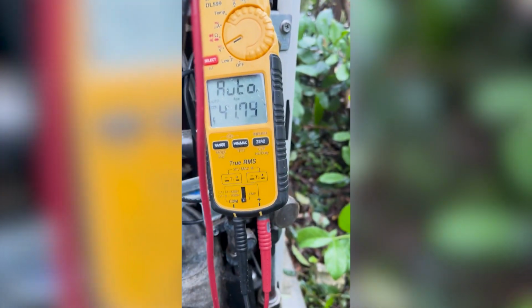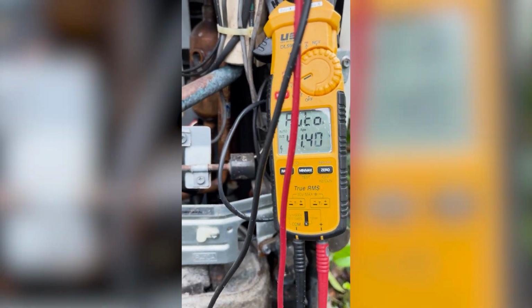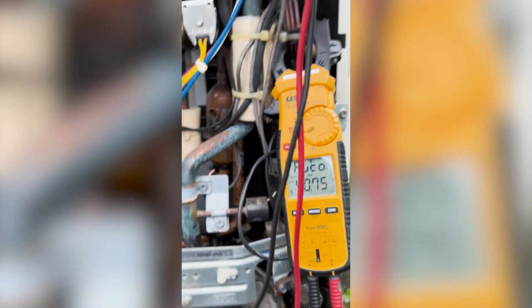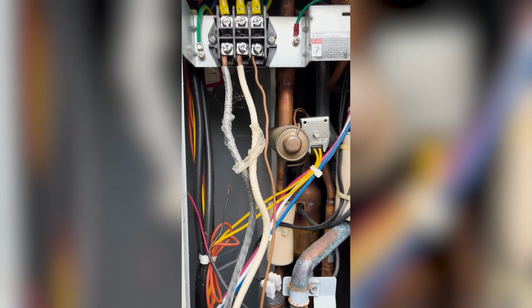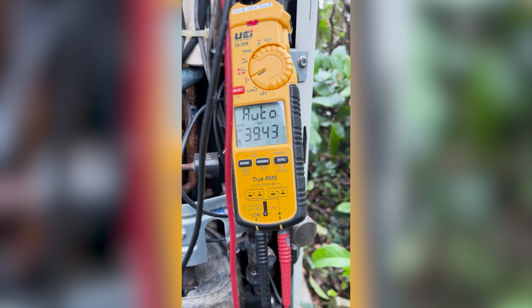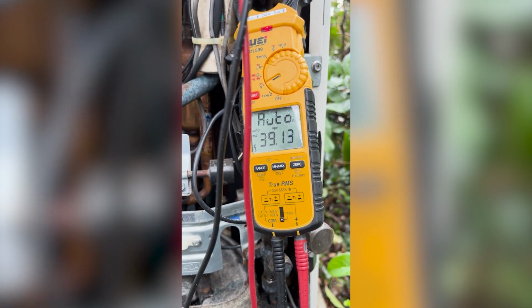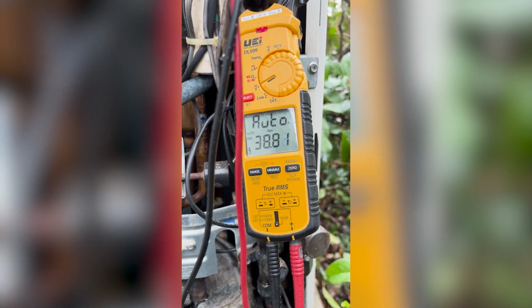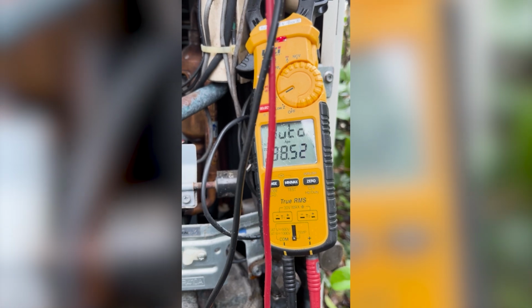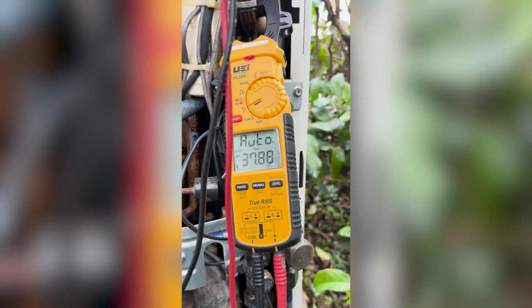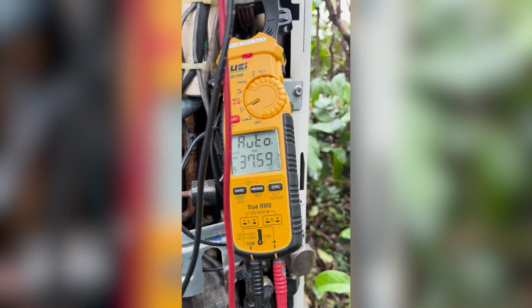This is important to notate because if you get in here on an inverter piece of equipment, you turn the power off to it, and you check your high voltage leads at your outdoor unit, you might think that you're safe and okay to start unplugging the compressor, start touching the inverter board, but you would actually be sadly mistaken, and unfortunately you'll get shocked. And it's a heck of a shock. Now this is only 208, 240, but you get into 460 volt equipment, you can easily get up to 1,000 volts DC stored on a capacitor charge.